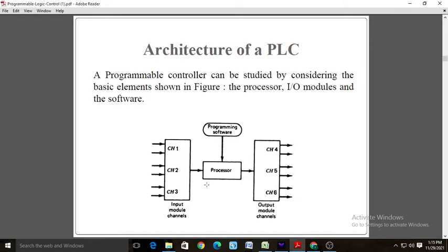Modular input output is split by compartment so that separate modules can be plugged in. An analog input card converts a voltage or current, anywhere from 0 to 20 milliampere, into a digital equivalent number that can be understood by the central processing unit.